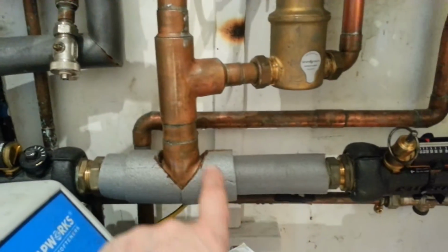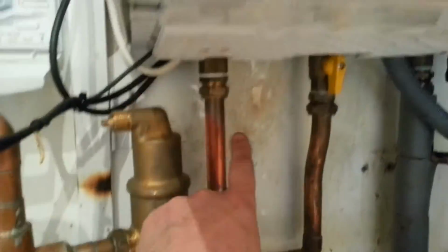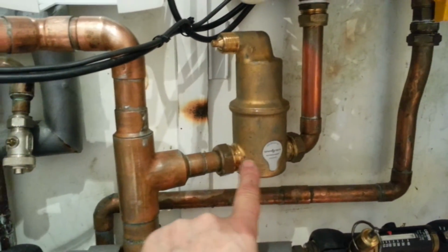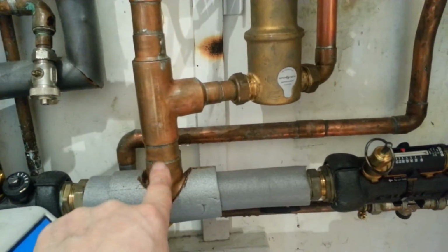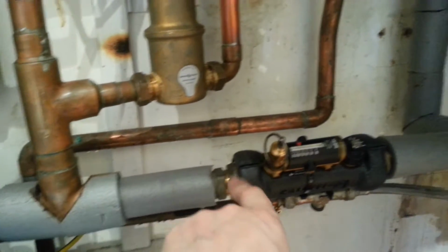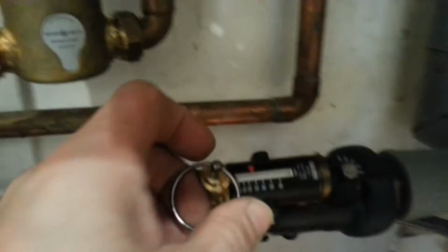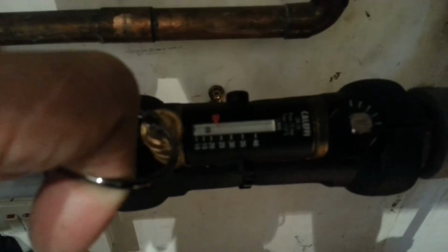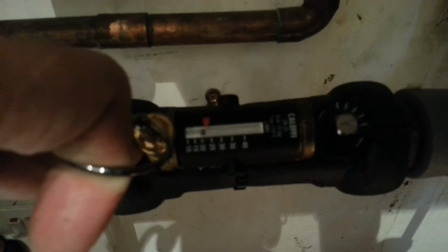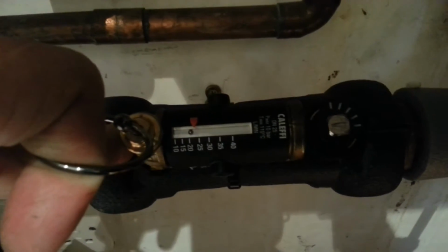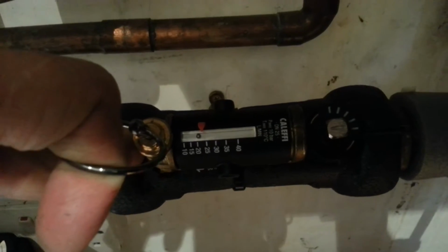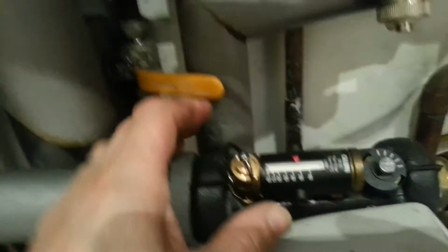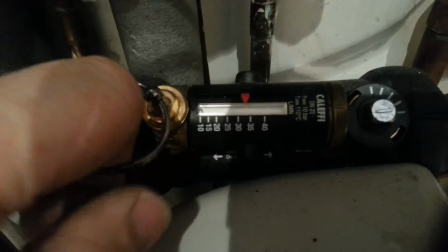So down here's my close coupled T again. Flow from the boiler, deaeration, close coupled T, return to my boiler, and a flow setting gauge. If I just operate this for you, you can see at all times we've got pretty much the perfect flow rate through the boiler, irrelevant of what's going on in the system. Flow rate this side can vary.